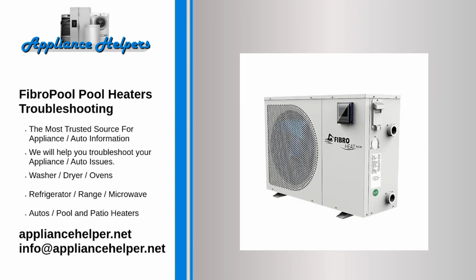If you're looking for help fixing your FibroPool pool heaters, look no further. Our comprehensive FibroPool pool heaters troubleshooting guide will explain common issues, provide tips, and show you how to read your model's error codes. Have you cleaned your filter lately? Monitor your PSI reading on your filter's pressure gauge. If the PSI is too high, clean your filter. Increasing pressure goes hand in hand with the decrease of water flow.